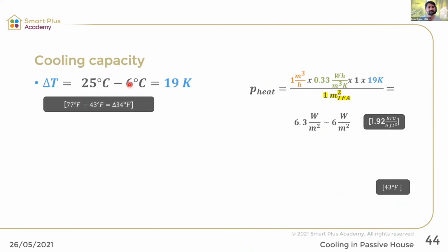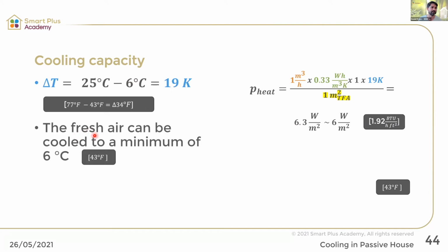25 minus 6 makes a thermal difference of 19 Kelvin. So the fresh air can be cooled to a minimum of 6 degrees, 42.8 Fahrenheit. And when we put that now into our formula, then we're having only 19 Kelvin thermal difference.